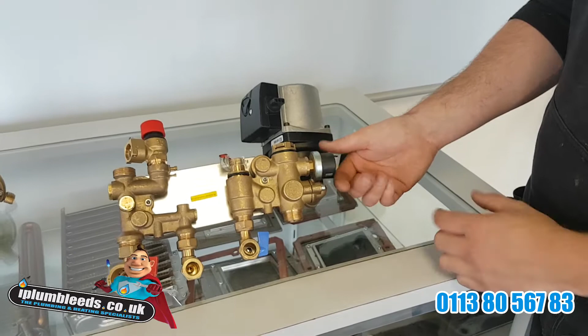This little device here is a pressure sensor, or a pressure switch should we say. Basically, your boiler needs a certain amount of water in it for it to turn on. My example to customers is you wouldn't turn your kettle on with no water in, because it'd break your kettle. So your boiler has to have a minimum of, on some boilers 0.5 bar of water, on some it's 1 bar of water. Once your boiler's got 1 bar of water in, this sends a little signal to the main board to say, right, the boiler is okay to turn on.